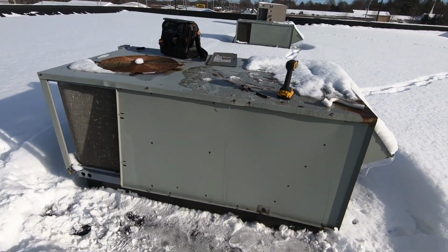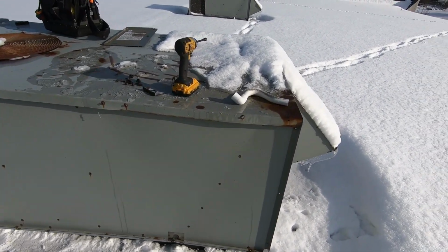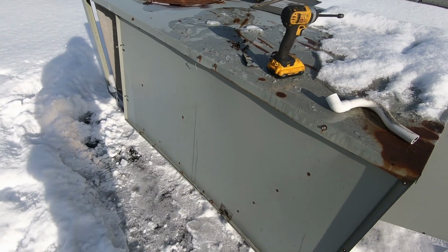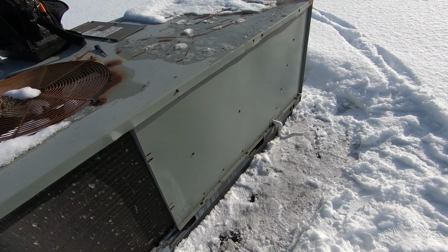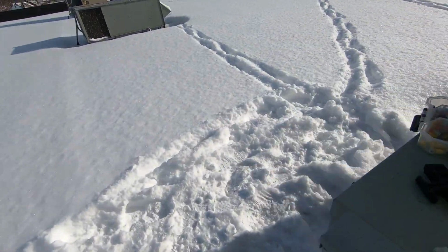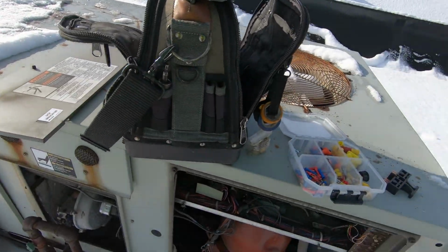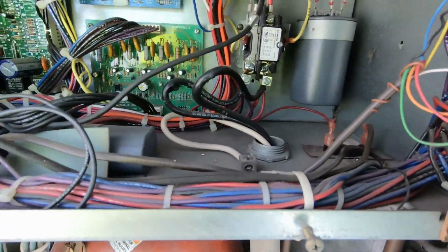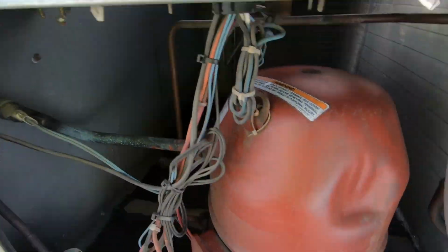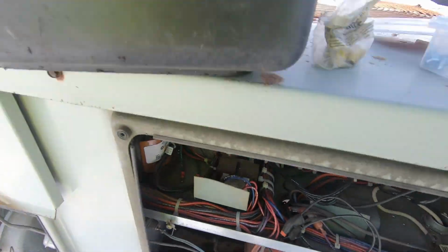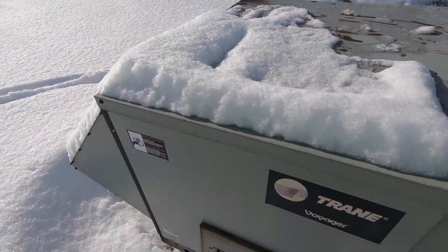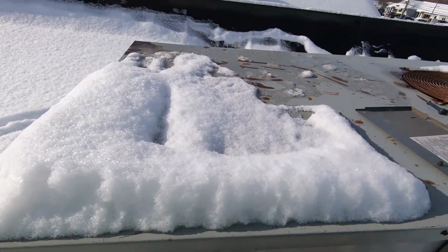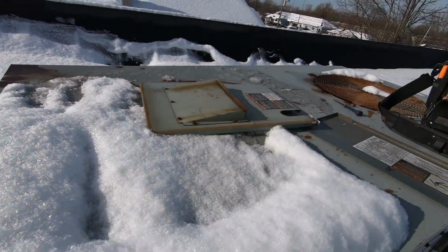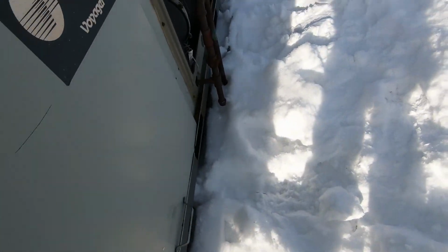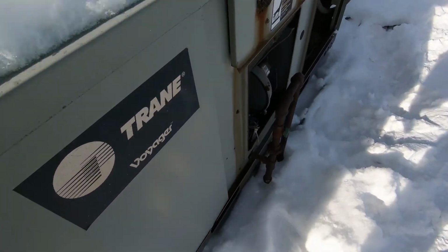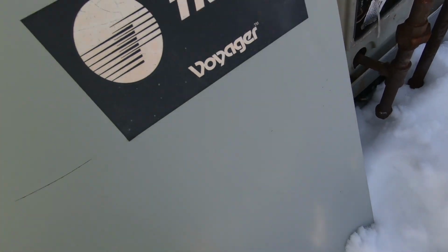I'm imagining it's got a bad igniter, and it's definitely gonna need that combustion blower just from the sound of it. Let me get this button back up and we'll move on. All right, I'll button back up over there. Give this electrical a quick look. I don't see anything jumping out at me. Gonna test that igniter. I know I smelled gas when I first popped up here, so I'm assuming it was trying to ignite. I don't know. It was calling, so it may have been locked out before I even got up here. And the gas smell might have been a figment of my imagination.